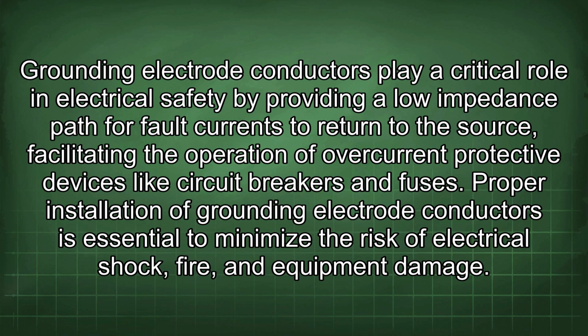Grounding electrode conductors play a critical role in electrical safety by providing a low impedance path for fault currents to return to the source, facilitating the operation of overcurrent protective devices like circuit breakers and fuses. Proper installation of grounding electrode conductors is essential to minimize the risk of electrical shock, fire, and equipment damage.